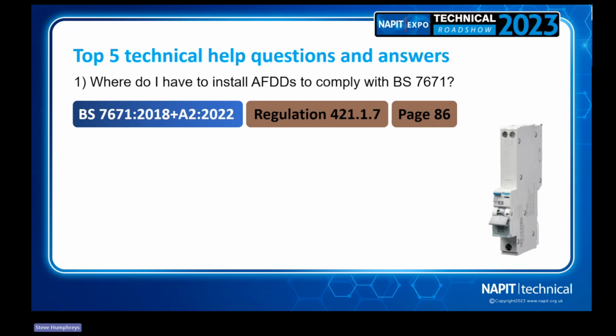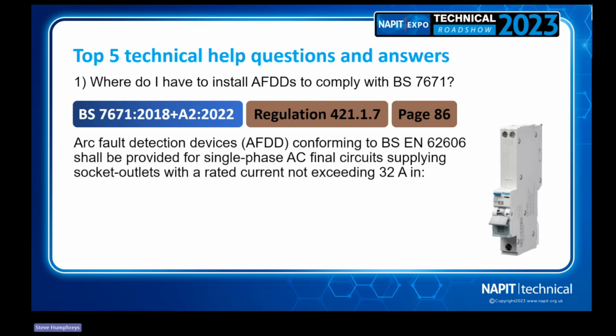So we see what the standards say. Here we've got regulation 421.1.7, and on page 86, what it tells us is this: arc fault detection devices conforming to BS EN 62606 shall be provided for single phase AC circuits supplying socket outlets with a rated current not exceeding 32 amps.